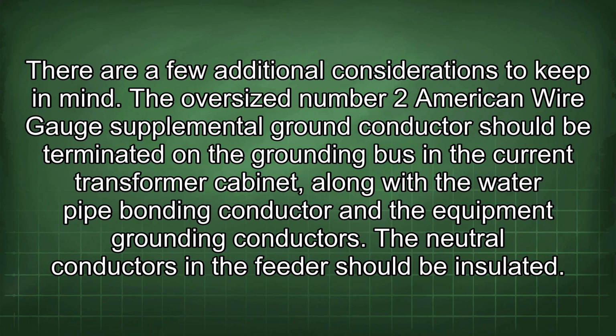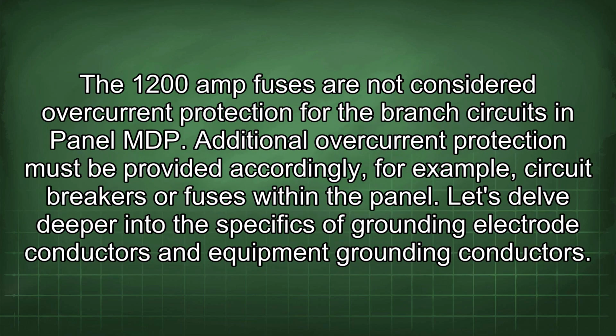The oversized number 2 American wire gauge supplemental ground conductor should be terminated on the grounding bus in the current transformer cabinet, along with the water pipe bonding conductor and the equipment grounding conductors. The neutral conductors in the feeder should be insulated. The 1200 amp fuses are not considered overcurrent protection for the branch circuits in Panel MDP. Additional overcurrent protection must be provided accordingly, for example, circuit breakers or fuses within the panel.